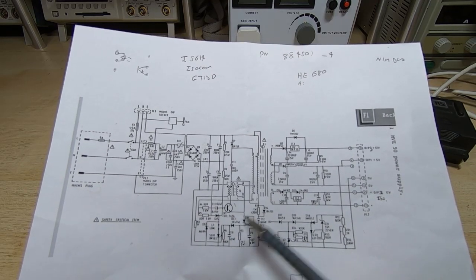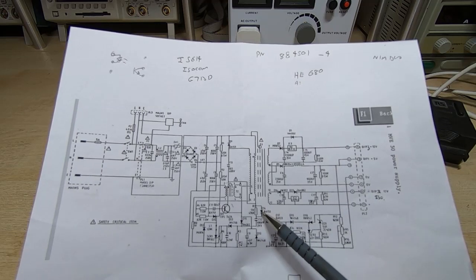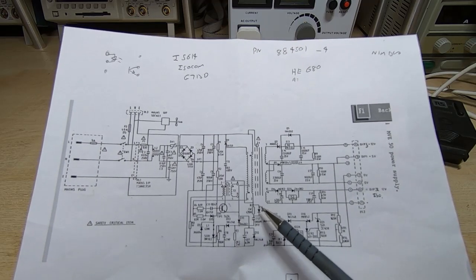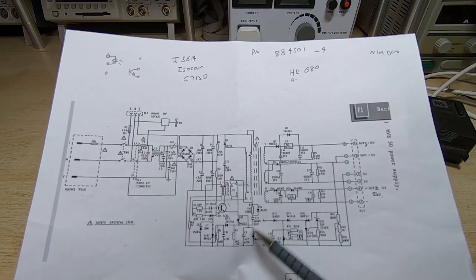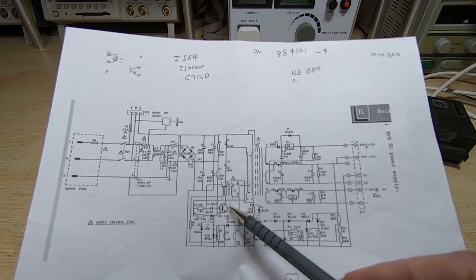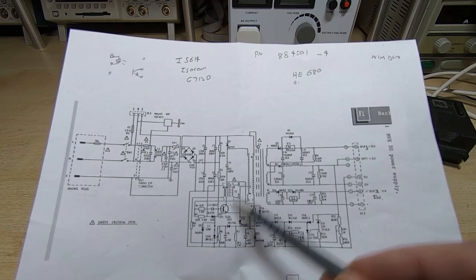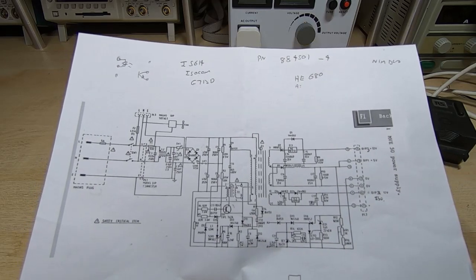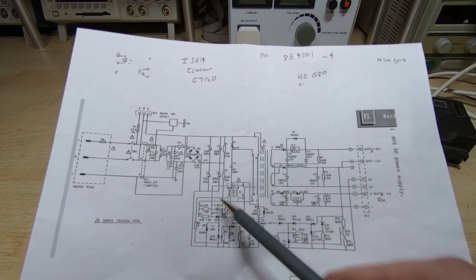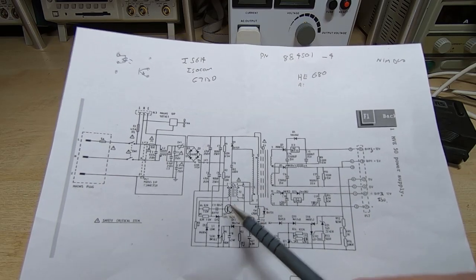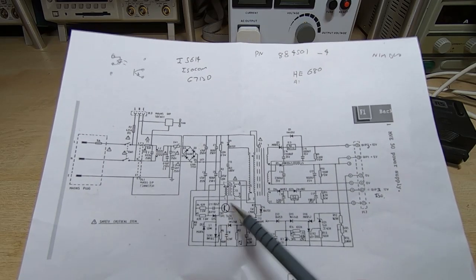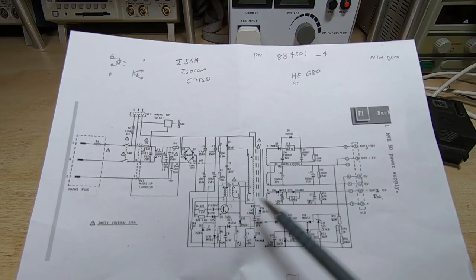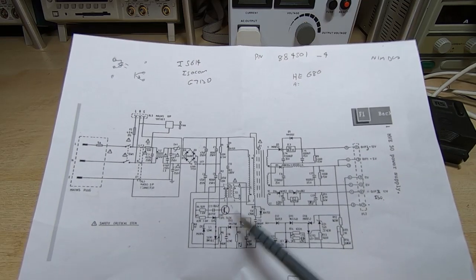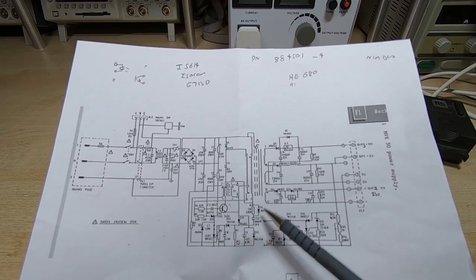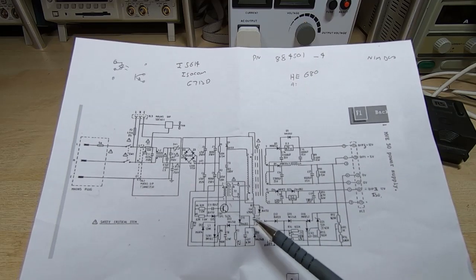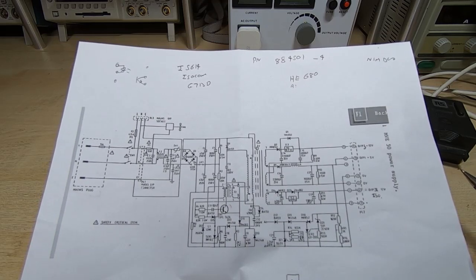So as I say, we can look at the snubbing circuits, and they can cause a problem. They are fairly highly stressed, and if the capacitor goes open circuit, it can cause the transistor to overheat, and if it goes short circuit, it can completely prevent the thing from running. If you're repairing one of these supplies and you find the transistor you replaced keeps getting very hot with no load, or it keeps failing for no apparent reason, chances are one or more of the snubber circuits aren't working properly and the transistor is being overstressed.